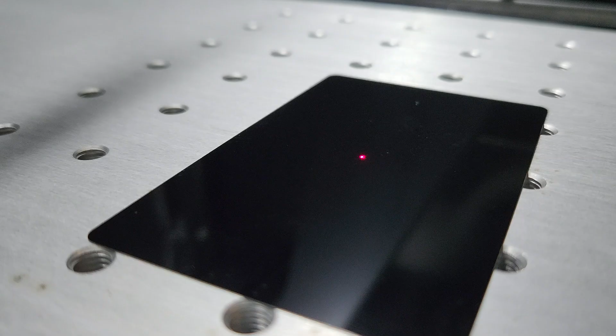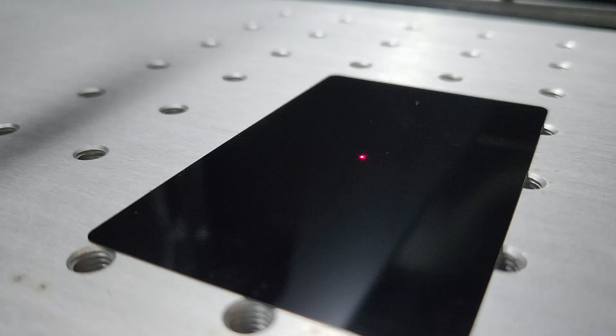I've set the increment to 1 millimeter, so each time the laser pulses, the head moves by 1 millimeter through the focal range. This test can be run multiple times, and the increment can be adjusted to a smaller value for increased accuracy if needed. Once the job starts, the laser will move upward in 1 millimeter increments, creating a grid-like pattern. After the job is complete, we will examine the card under a microscope to gain a clearer understanding of the results.